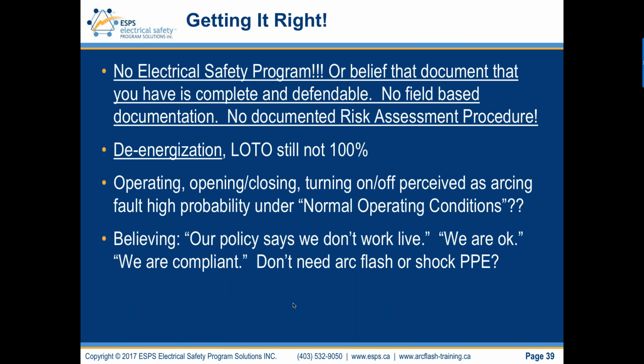I've audited too many of these documents and advised clients that they aren't complete. They're not defendable, right? You just can't copy content out of 70E and Z462 and call it an electrical safety program. What was highlighted in the 2015 editions of both those standards is that you shall have a documented electrical safety program. So if you don't have one, you need one. If you are telling your workers and you're telling the regulator that your practices are based on 70E and Z462, and then there's no field-based documentation. So the qualified person, or what I call the qualified electrical worker, doesn't have to fill out anything in the field to validate that they're applying the controls that you need them to apply to achieve the residual risk level.